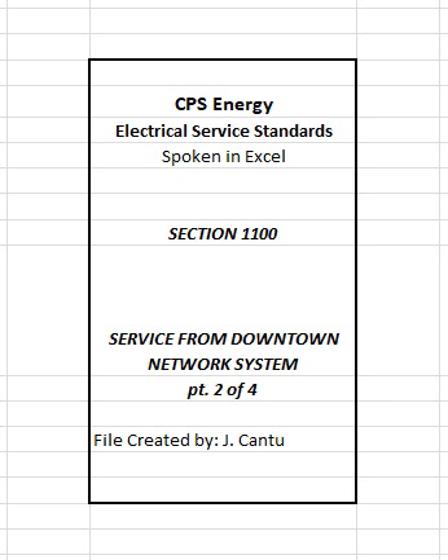A 12-inch thick reinforced concrete is a standard requirement on a pour-in-place design. In cases where 8-inch CMU is approved, it shall be filled with 2,500 psi concrete with reinforced rebar. The roof must meet the requirement of the H20 highway loading specification. Customer shall pour concrete in a manner that will eliminate air voids. No existing clay tiles, sheet rock or stucco wall of any type shall be used as interior vault walls.